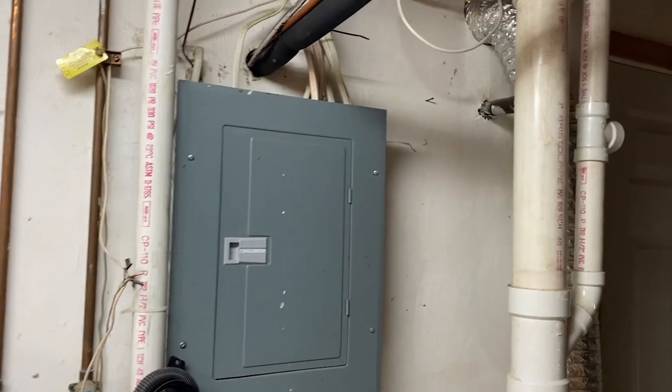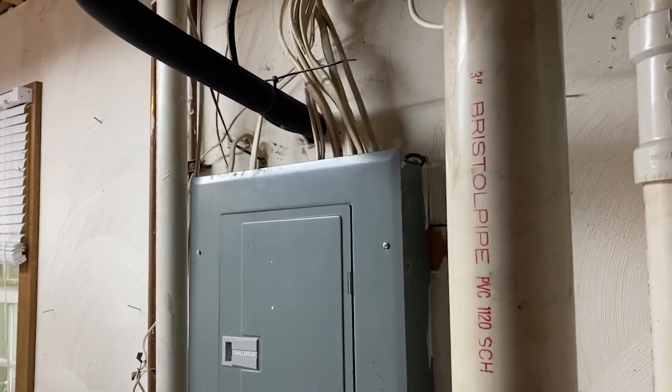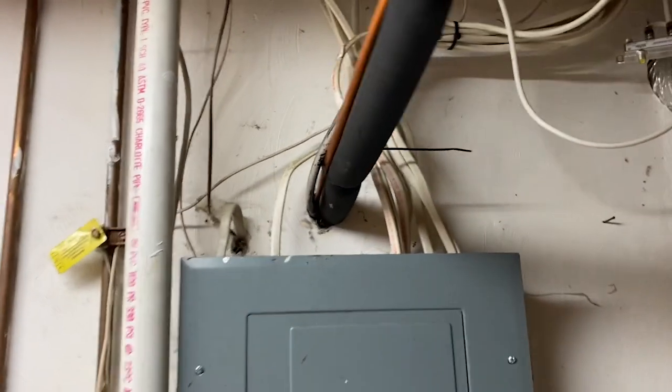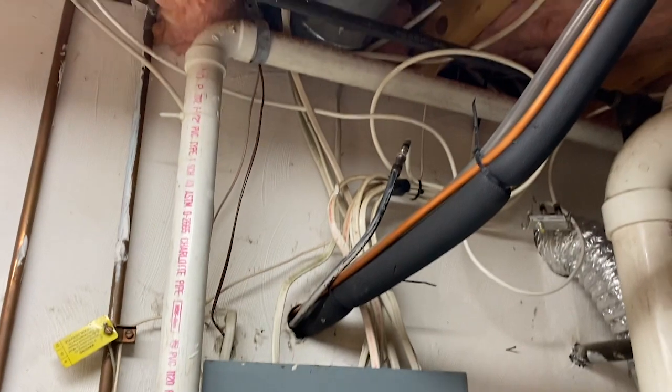Hello and welcome to Moving Violations. This is Russell Blank, your NEC consultant for EC&M Magazine. I spotted a couple issues with this panel board. One is these refrigerant lines up above are in the dedicated space, and also we've got some encroachment into the working space.